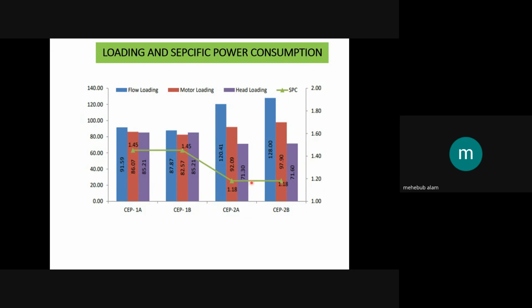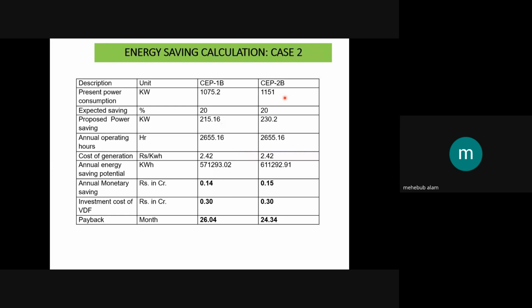The specific power consumption for the two CEPs, 1B and 2B, has been measured, and the result is shown here. As told, the specific power consumption is to be reduced, and that has to be done by reducing the discharge pressure. The present power consumption was around 1075 and 1155 for CEP 1B and 2B respectively, and the expected saving is around 20%. After calculating this and considering a generation cost of around 2.4, the monetary saving will be around 0.144. If we consider the investment, the payback period will be around 2 years, 24 months to 26 months.